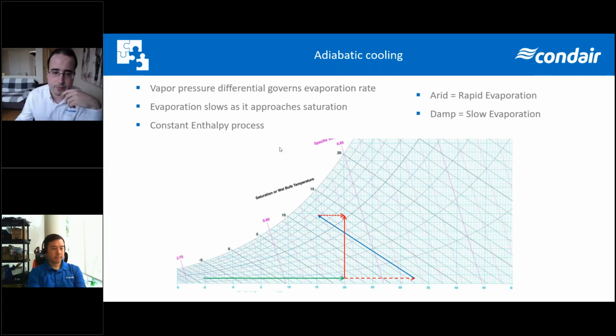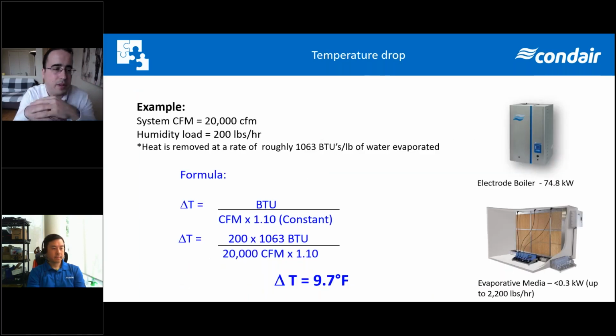When you evaporate water in the air, you also get your cooling. To give a quick example, if you have 20,000 CFM and a load of 200 pounds, in this case humidity, but it will be similar for cooling: with electrics, you get 75 kilowatts to evaporate 200 pounds an hour. While with a media system, as you can see in the picture below, it's only around 300 watts, and you can get up to 2,200 pounds per hour. And you can see with the adiabatic system, for 200 pounds an hour, you get a delta T of 10 degrees Fahrenheit. So you also get adiabatic cooling.